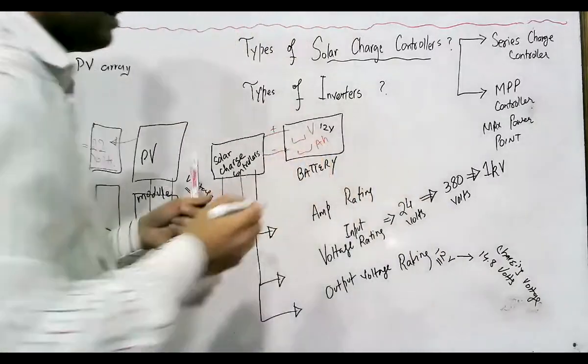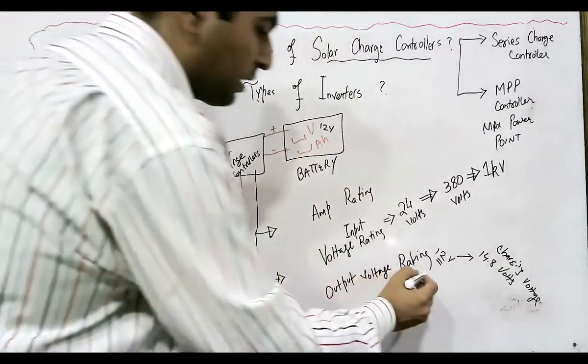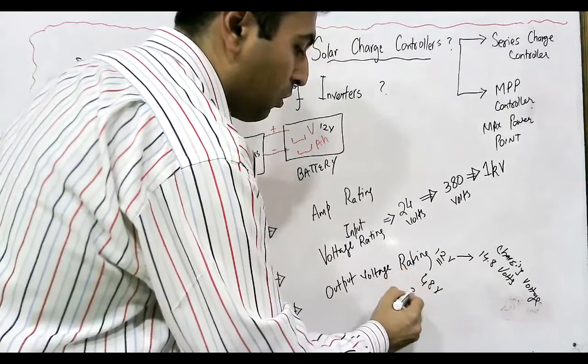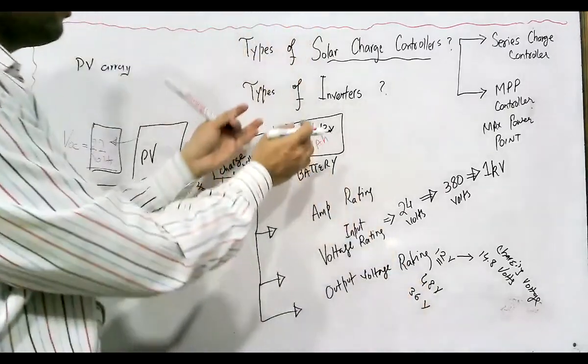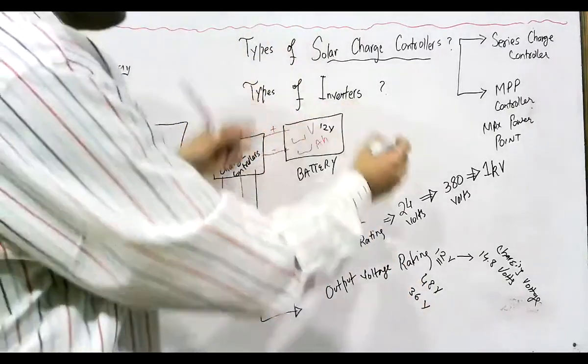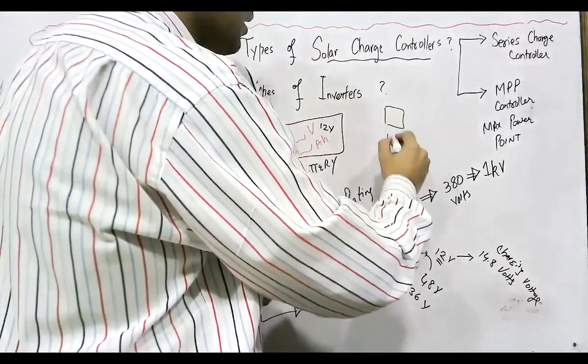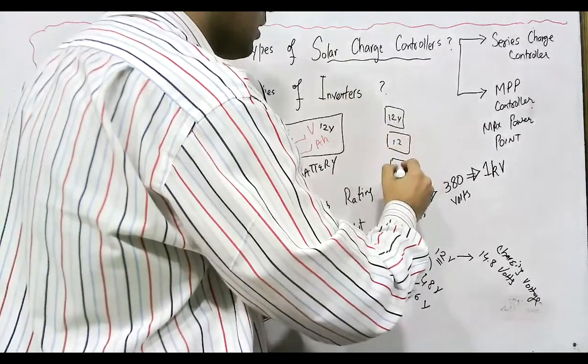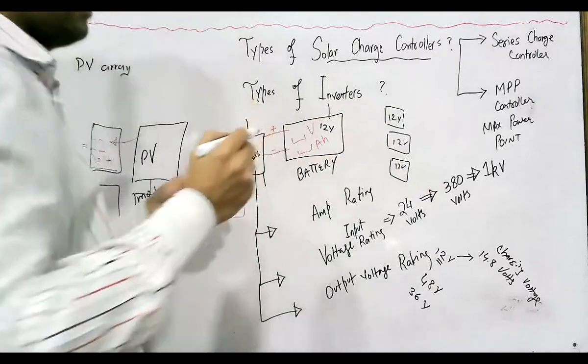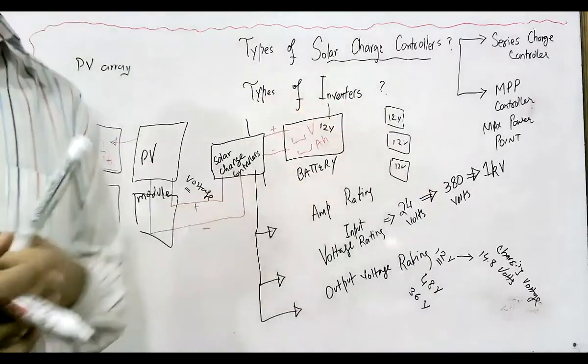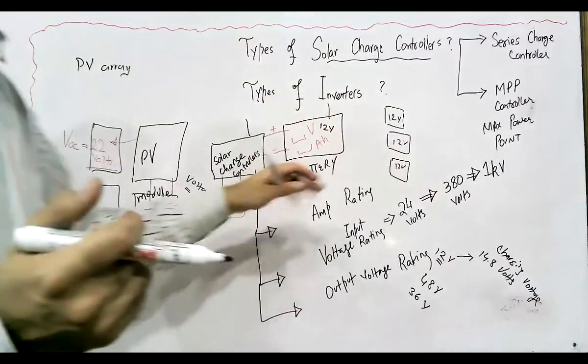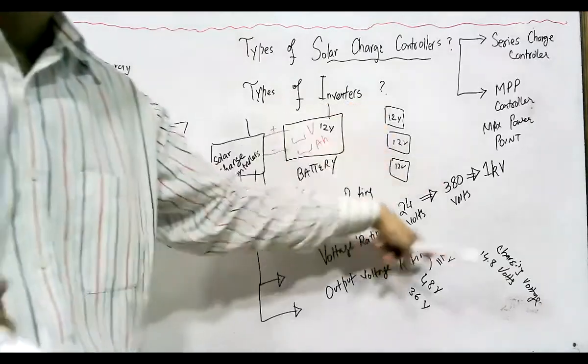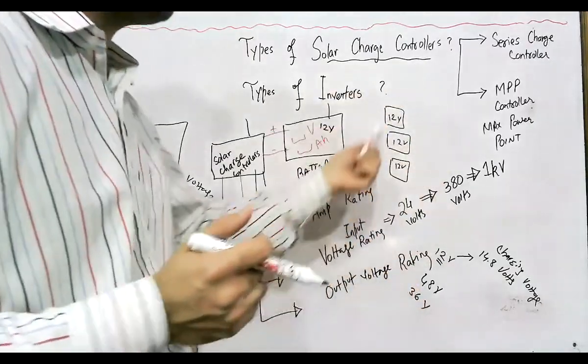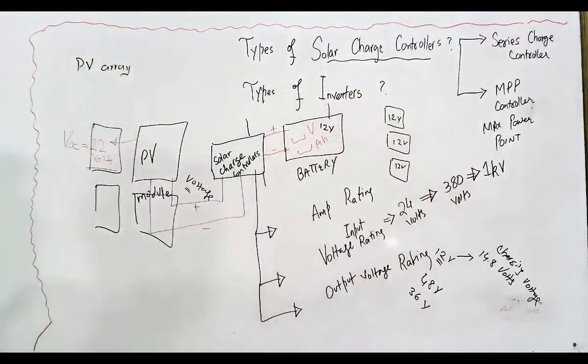And if its output voltage rating is 48 volts or 36 volts, then you have to connect 3 batteries in series, 12 volt batteries in series, so you get 36 volts to charge those batteries. It entirely depends on its rating and whatever battery bank combination you are going to have.